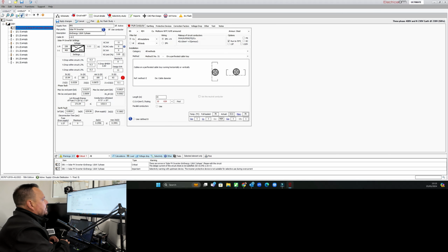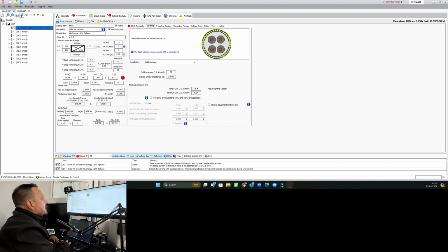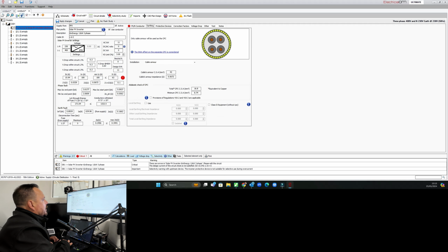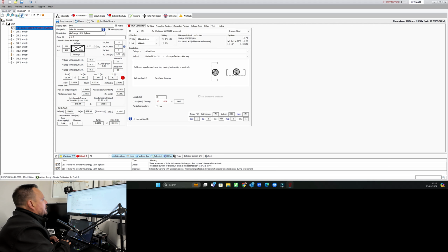So we've got the phase neutral and earth. We've got our 10 mil sizing. You can see we've got a warning on that. It's actually saying we might want to consider bigger, so we'll look at that in a minute. If we have a look further down now, we can look at the earthing. So we're going for the cable, armour, and a separate conductor. Sorry, the core of the cable. So pop that on there, and we've now just got the warning here again around the size of the cable that we're using on our perforated tray for the 11 kilowatt PV inverter.